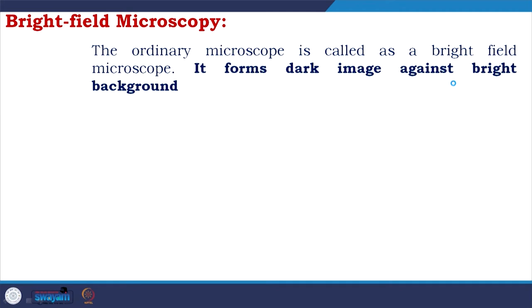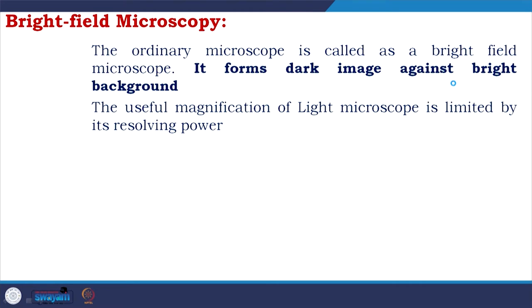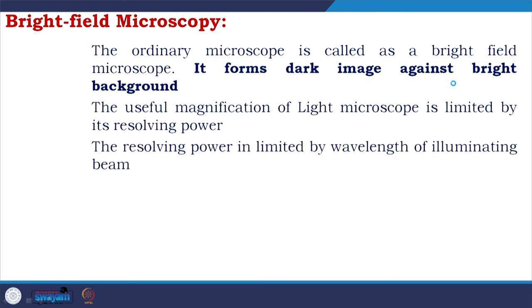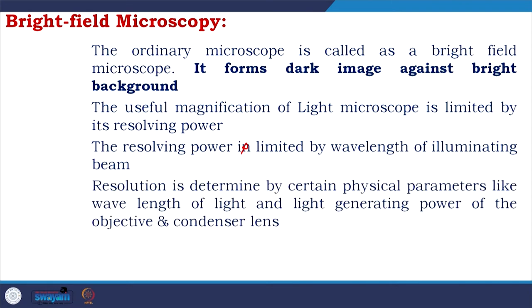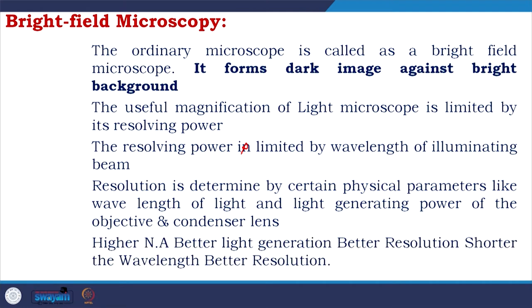The ordinary microscope is called a bright field microscope — it forms a dark image against a bright background. The useful magnification of a light microscope is limited by its resolving power, which is limited by the wavelength of the illuminating beam. Higher numerical aperture gives better light gathering and better resolution; shorter wavelength also gives better resolution.